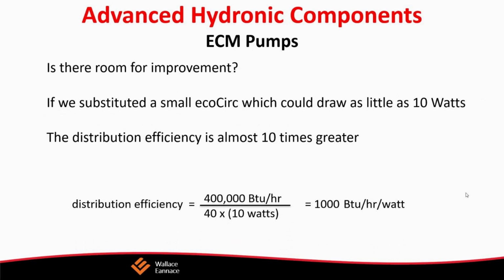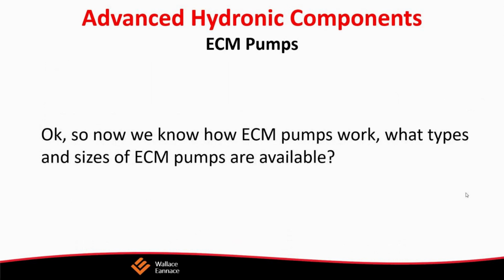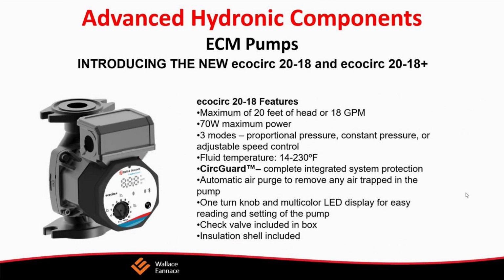So if you compare the two, the hydronic system distributes the heat almost 4 times more effectively than a forced air system. Its efficiency is effectively 4 times greater. What that tells us is that water is dramatically superior to air for heat delivery. But even after considering that, is there room for improvement? Consider this beautiful house here, and we look inside their heating plant, and you see all these circulators lined up.